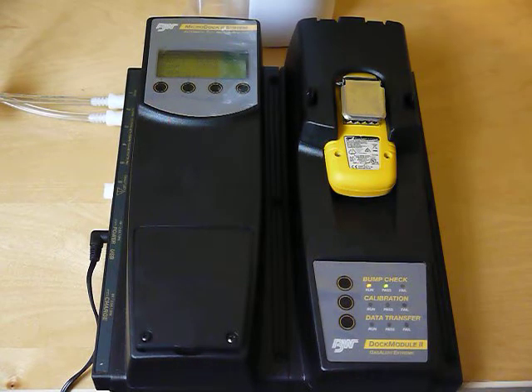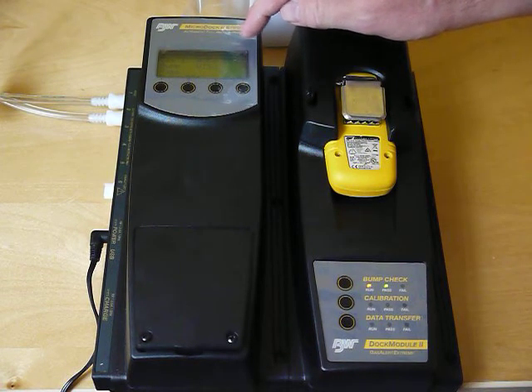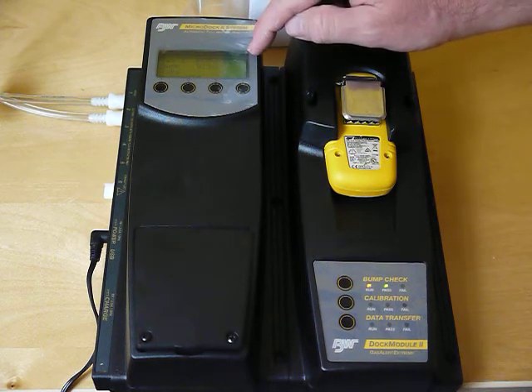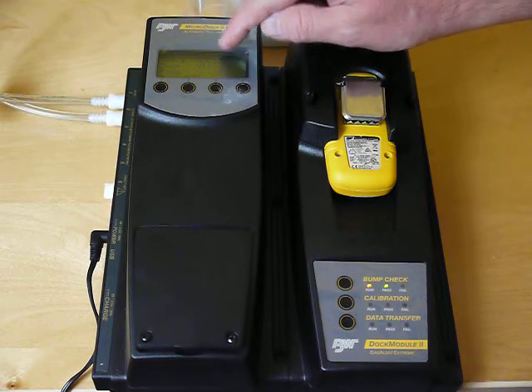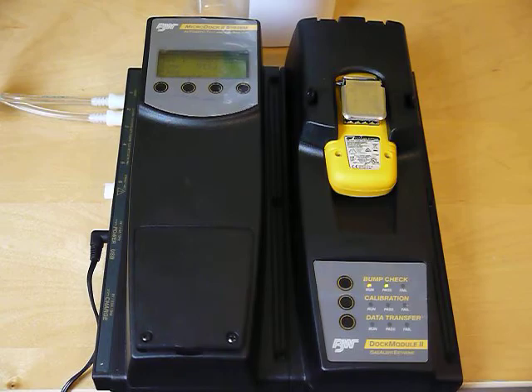Right now it's at about 40 seconds left on the purge. It gives me check marks for the SO2 sensor, and the audible and visual alarms as well. And it would record that onto the flash drive, or onto the SD card.